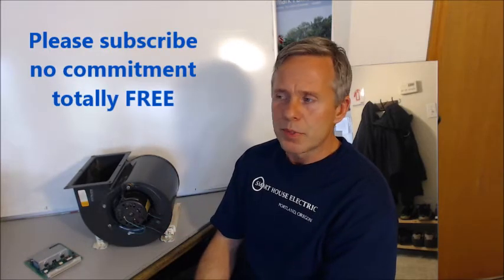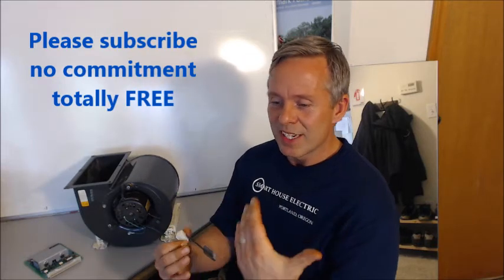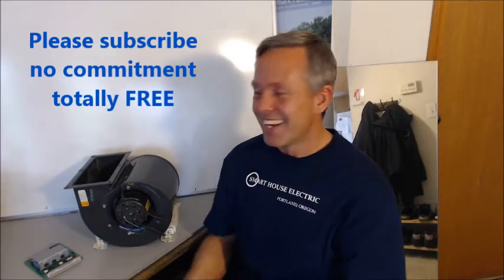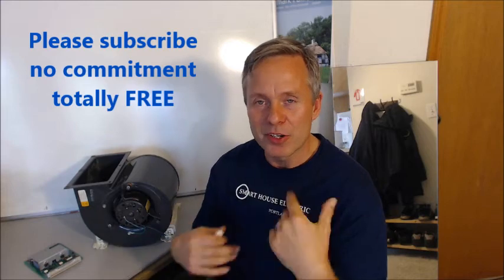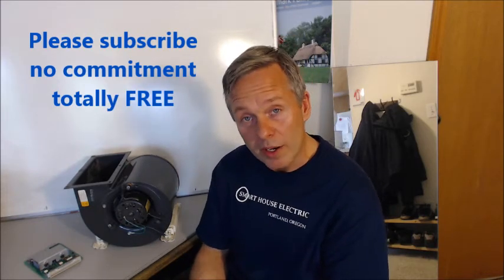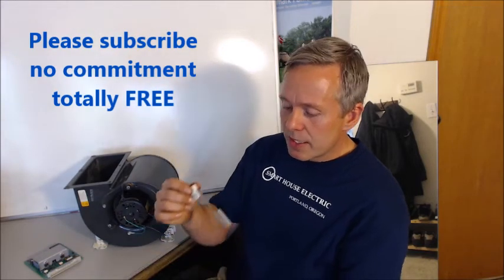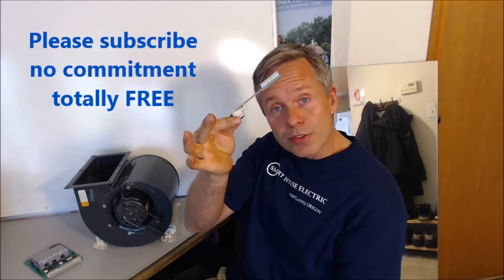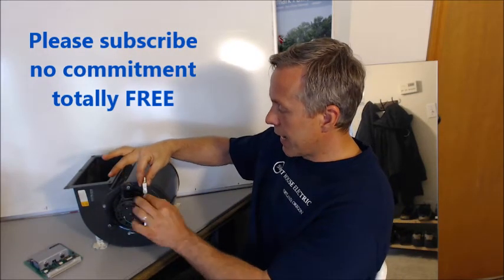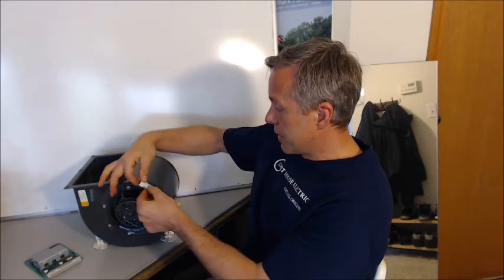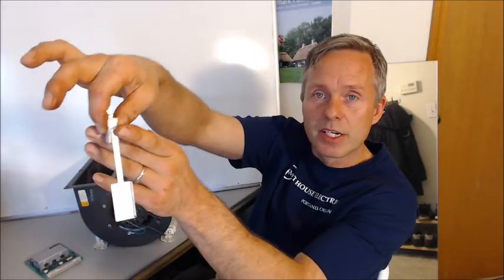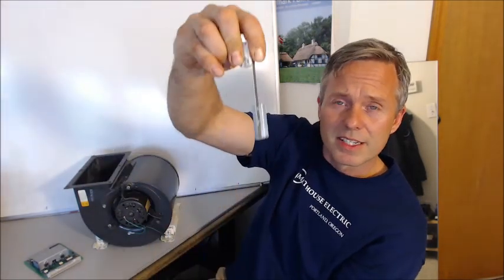And then as a little bit of a different problem than with the error code 40, here, if the fan keeps on spinning, it could also be a software issue, such as the machine not knowing electronically what type of machine it is, which can make it get stuck and just keep on turning the fan and causing an error code 41. But more commonly, it is again the airflow switch causing this problem. Mechanically, it gets stuck on the side of the holder that's holding this airflow switch, stuck in the on position, and causing 41.